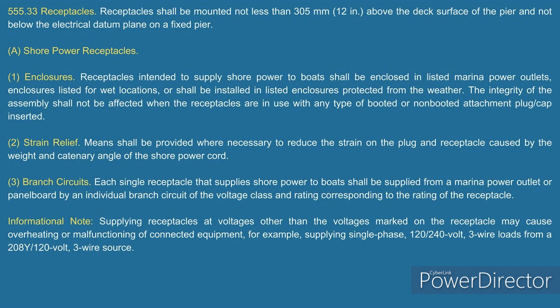So when they are clarifying some of these individual branch circuits, they're basically taking it from the definition of a branch circuit and telling you you've got to have a receptacle there. Otherwise, they don't mention a receptacle, because you're connecting to what? Utilization equipment, which is hardwired.